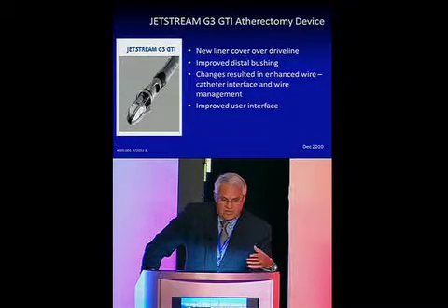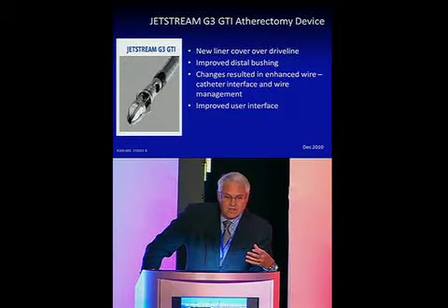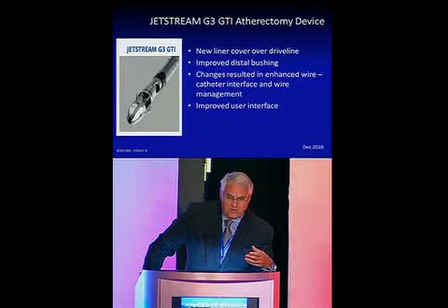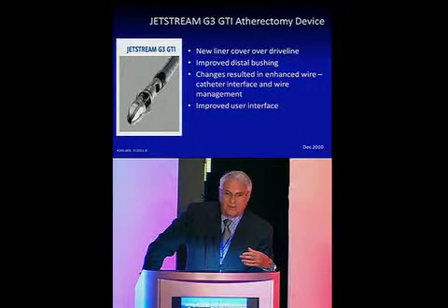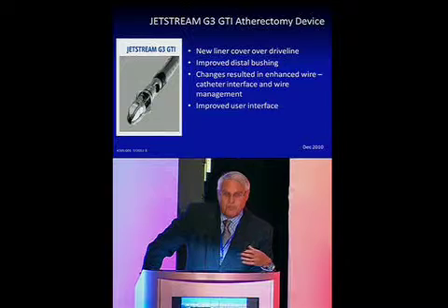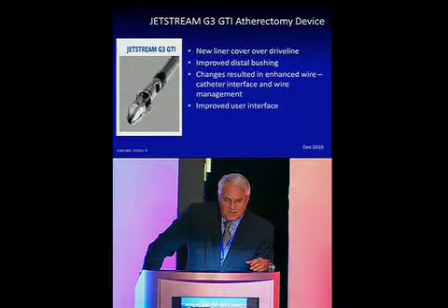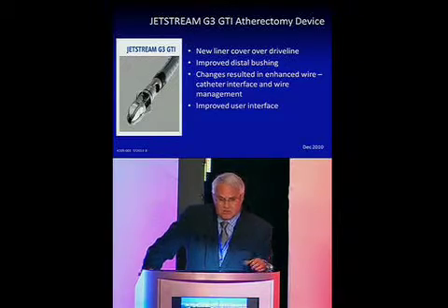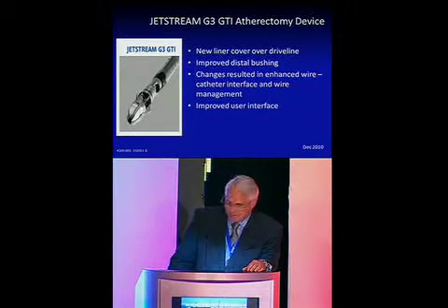There were some changes in terms of the distal bushing with some of the changes in the drive shaft. That has allowed for greater improvements in trackability of the device. This is an 014 compatible system, and there were some improvements in user interface with the iteration that took place in 2010.